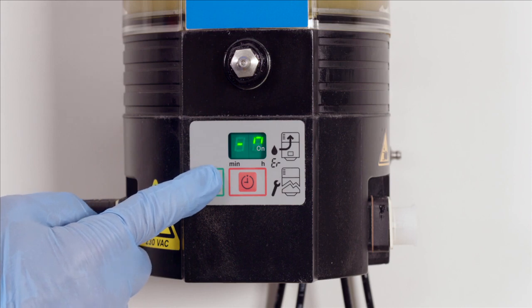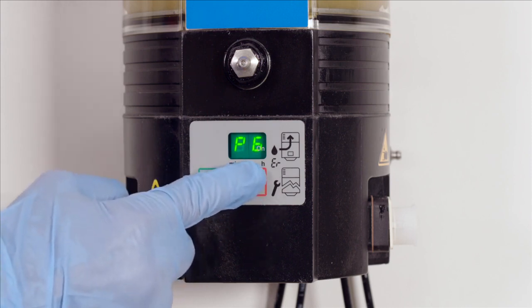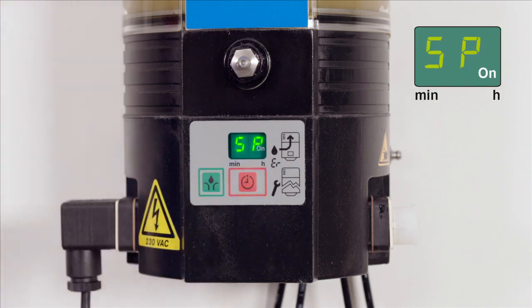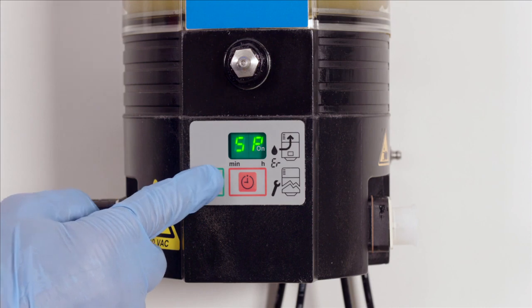P6 is now displayed. P6 defines how the pump will start when it is switched on, either with a pause time, SP setting, or a lubrication cycle, SO setting. Select and confirm.